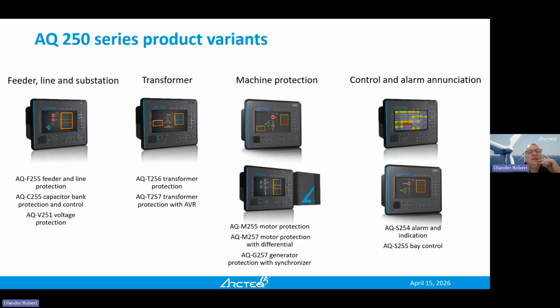And here you see a little bit, so the 200 series is targeted at the distribution network. We have also line protection like line differential and distance protection in the device. But we also see that this type of functionality is more and more needed in the distribution network. So at the moment the functionality we will look at is typically targeted at 100 kilovolts or below.